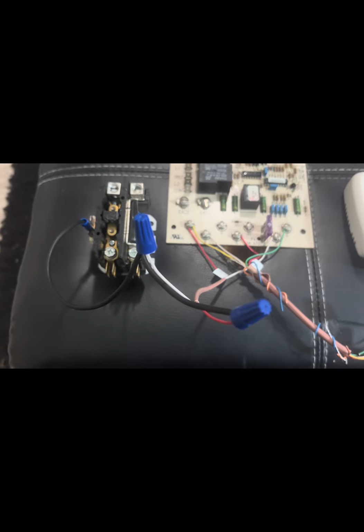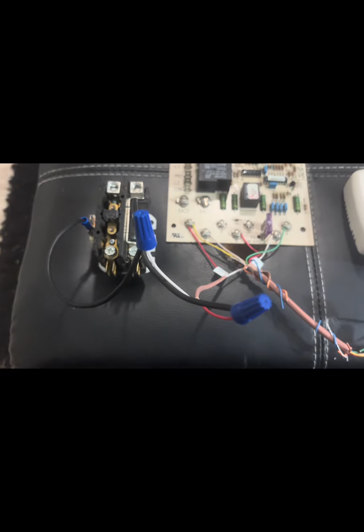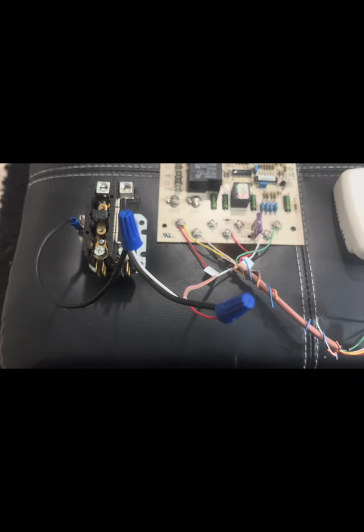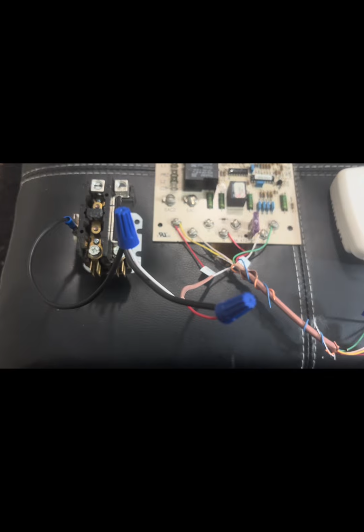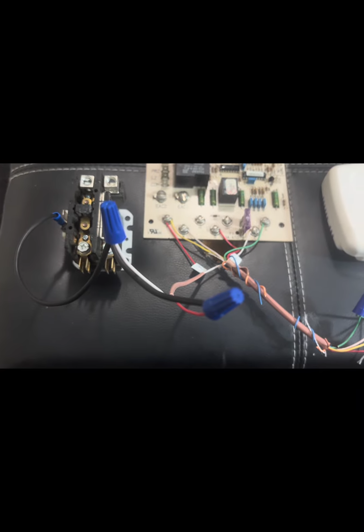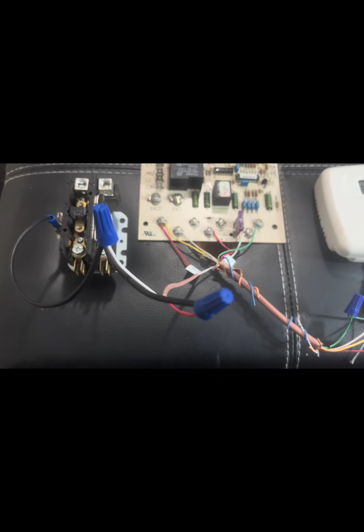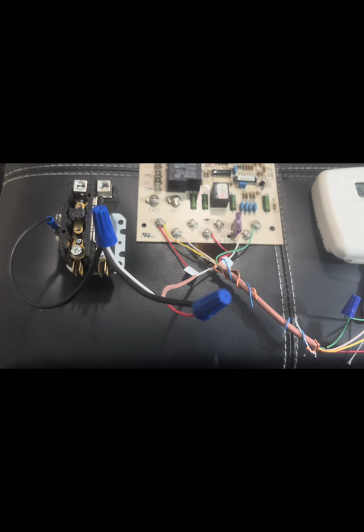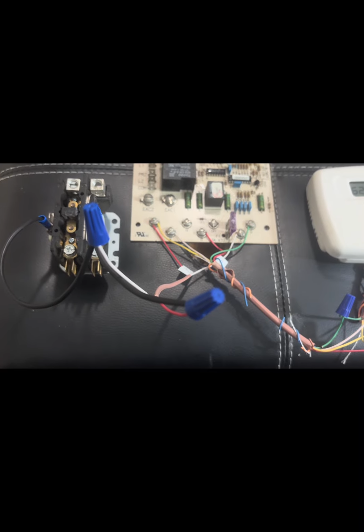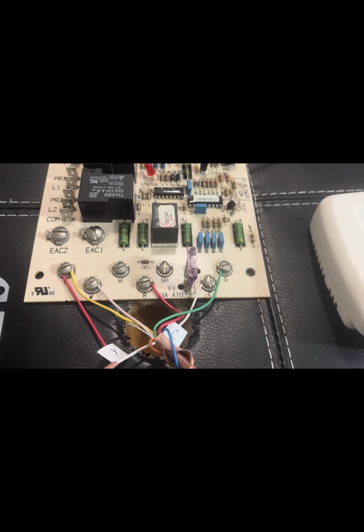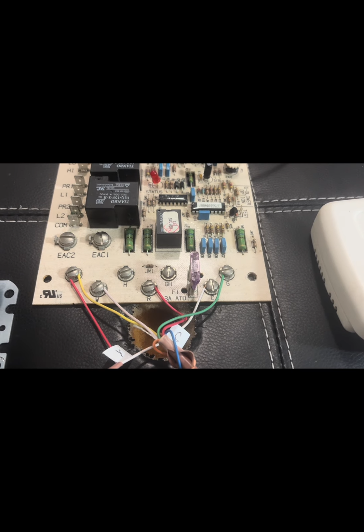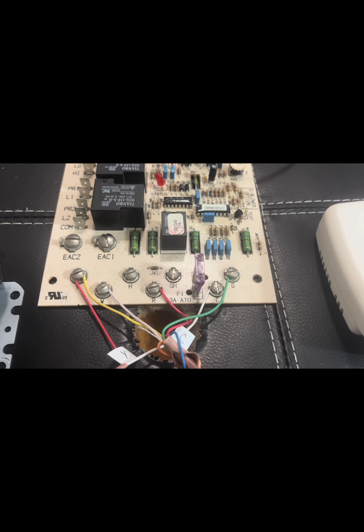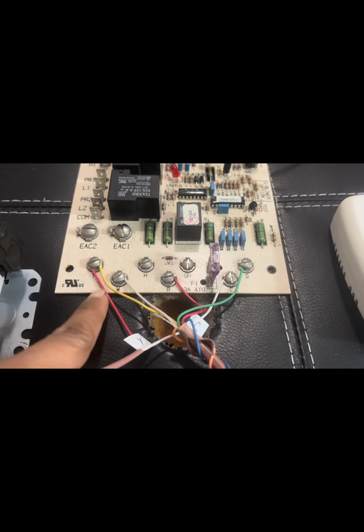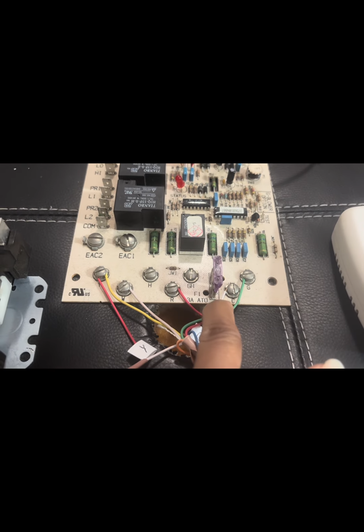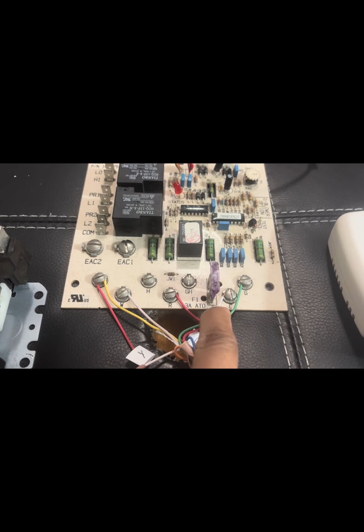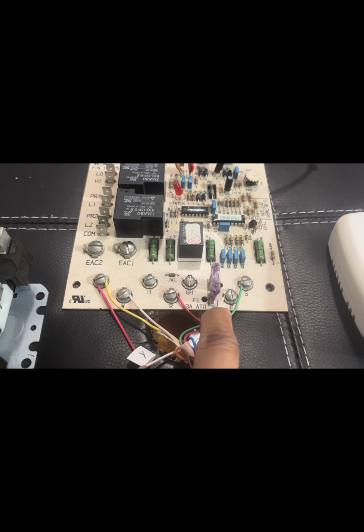That's it. A straight cool condenser only needs 2 things to run: a call for cooling, which would be your Y, and a power path back to the transformer, which will be your C. When C and Y complete the circuit, it energizes the safety circuit inside the condenser, your contactor coil, which pulls in the contactor. Now let's move to where the 2 condenser wires connect on the control board. The condenser wires go right here and right here. Your outdoor Y wire to the Y terminal and your outdoor C wire to the C terminal.